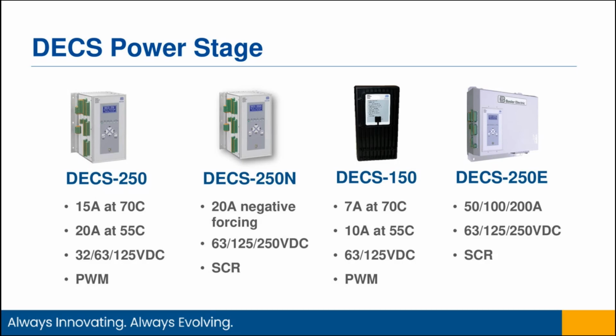It is capable of 20 amps, but we add negative forcing. So in that SCR diagram I showed you before, we were only rectifying in the positive direction. We do have the capability to also do it in a negative direction, which gives us better responses upon load rejections and times when we need to pull excitation down in a very quick manner. So there are some applications for a negative forcing power stage, which I'm sure we'll cover in future seminars.